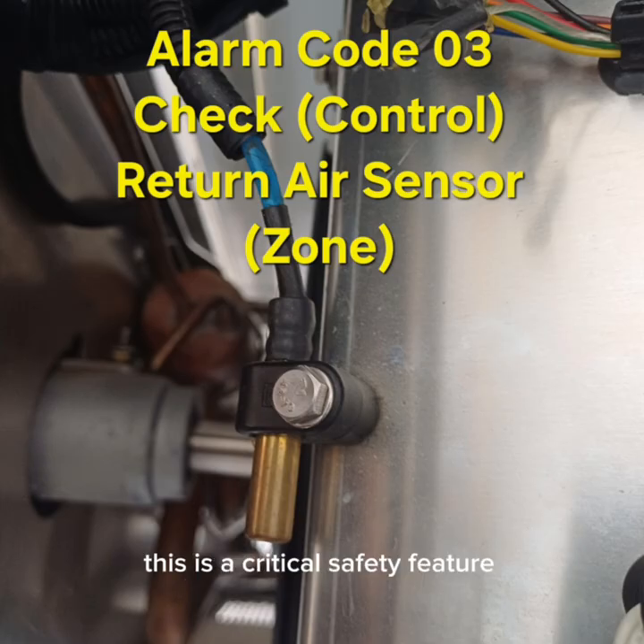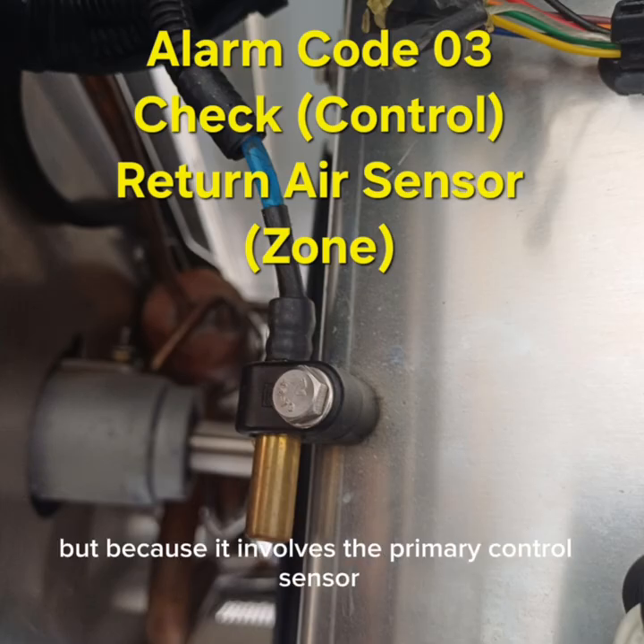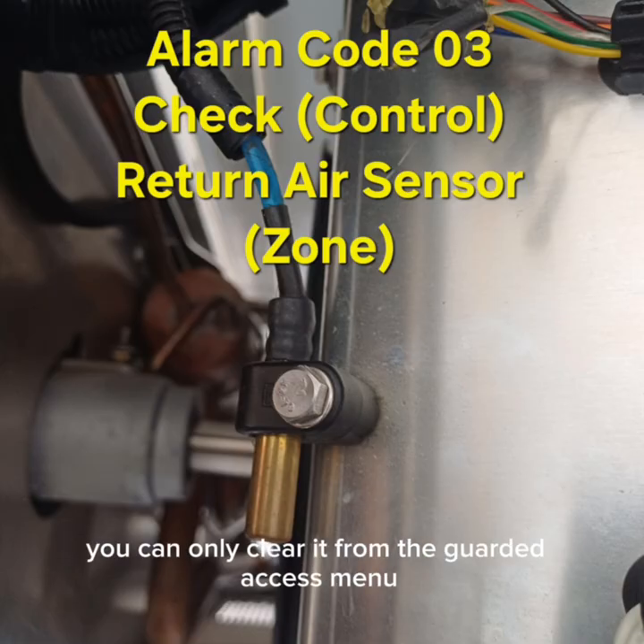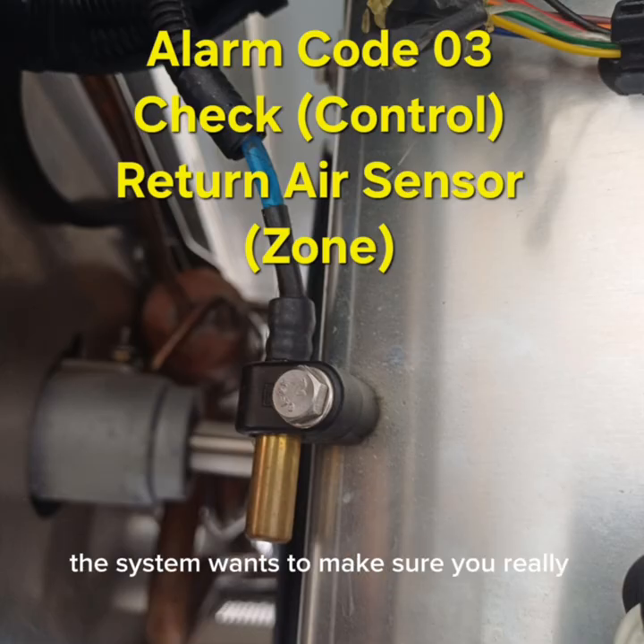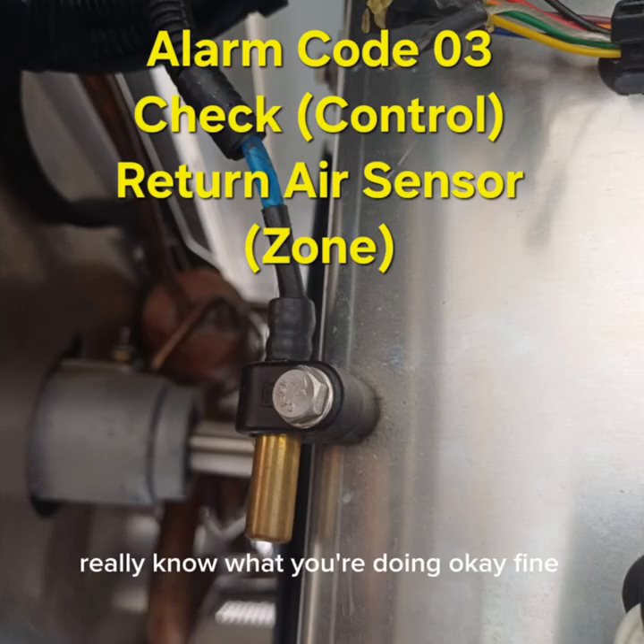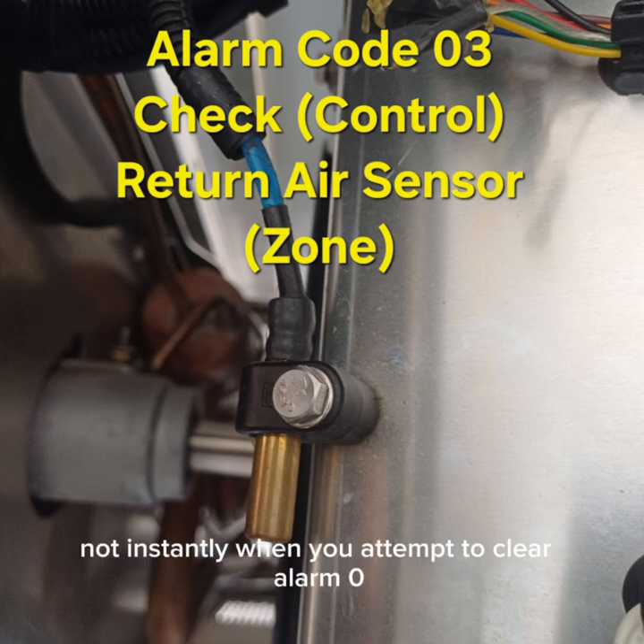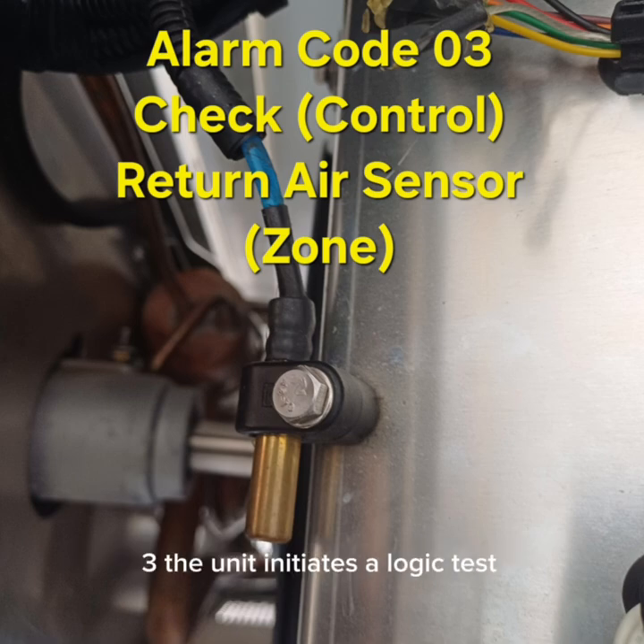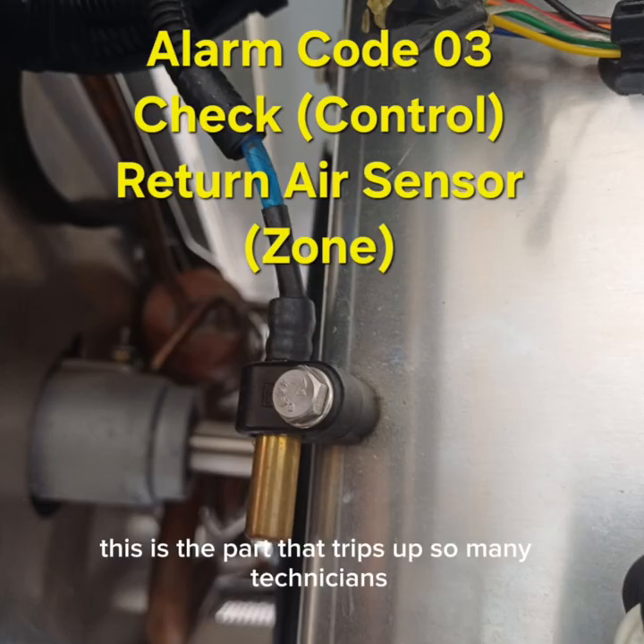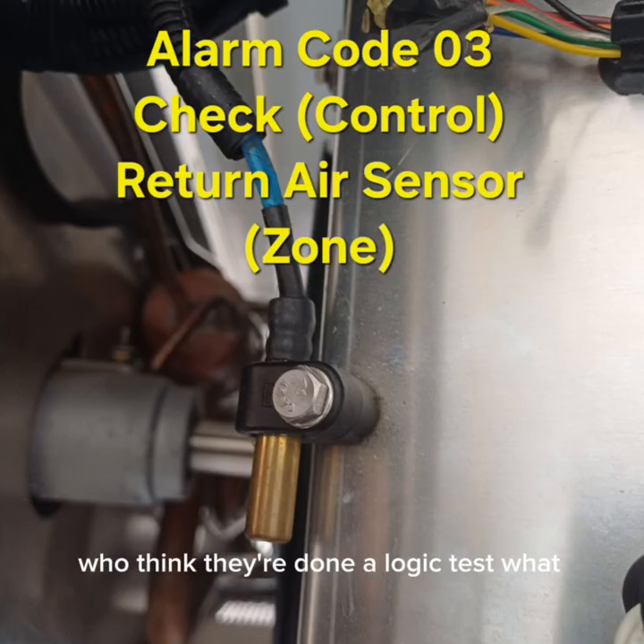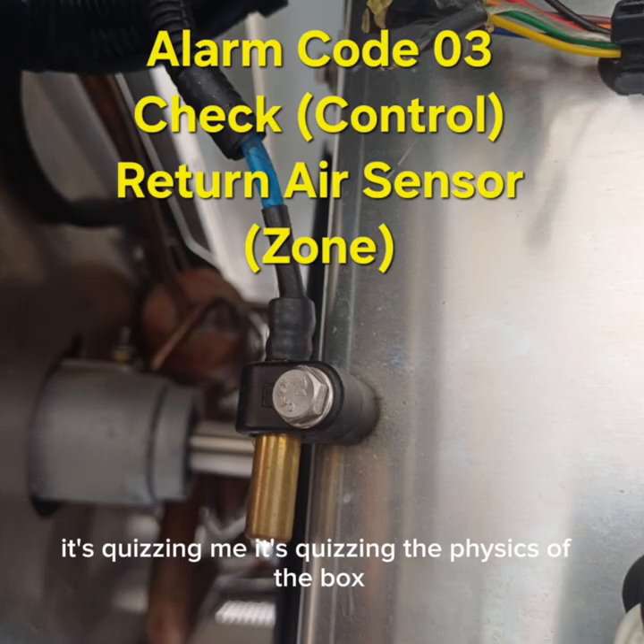This is a critical safety feature. Alarm code 03 is a check alarm, but because it involves the primary control sensor, you can only clear it from the guarded access menu. The system wants to make sure you really, really know what you're doing. Okay, fine. I'm a pro. I go into guarded access. I hit clear. Does it go away then? Not instantly. When you attempt to clear alarm 03, the unit initiates a logic test. This is the part that trips up so many technicians who think they're done. Logic test? What? Sure. It's quizzing me. It's quizzing the physics of the box.